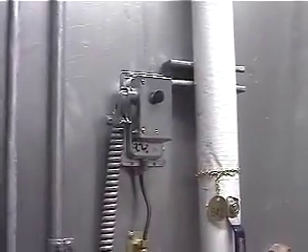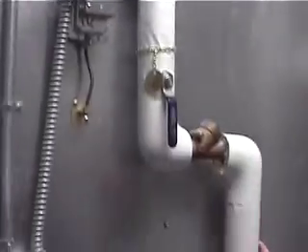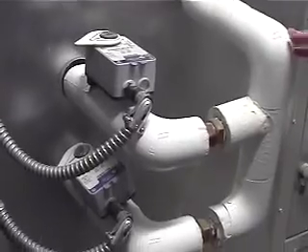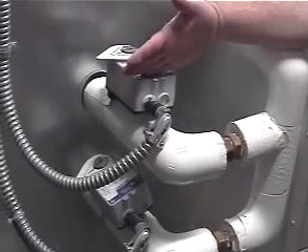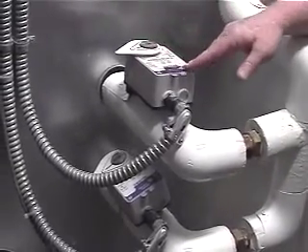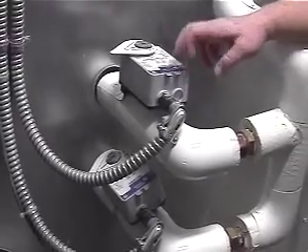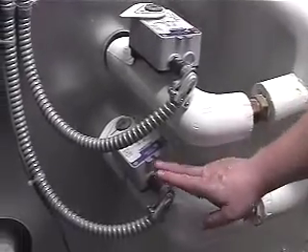Here you have your typical high duct static sensor. It's set up at 5 inches on both of them. So that's your high pressure alarm. This right here is going to be your makeup, or well, the evap section. The first one I believe is your makeup, and we can look in there to double check. I believe this is your makeup. This is your flush, and this is your drain. By default, these fail closed, this fails open.